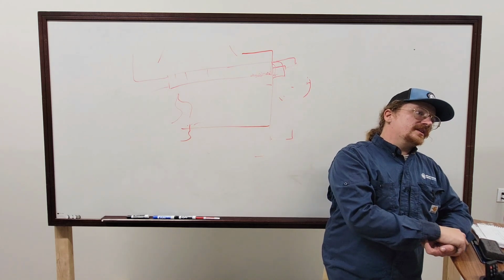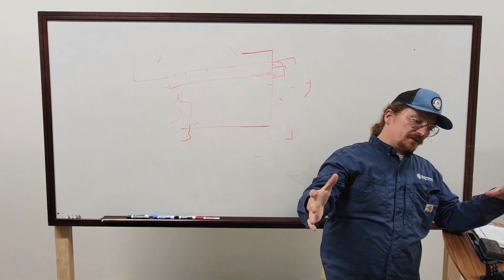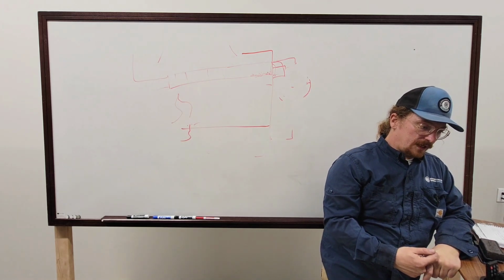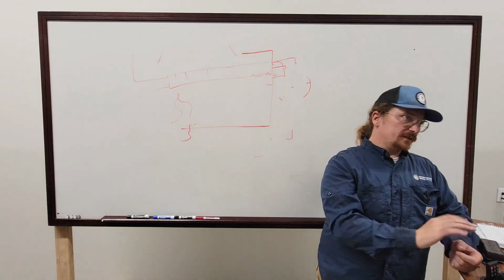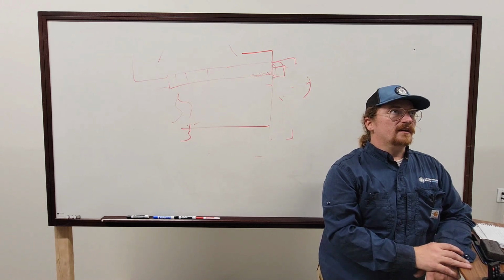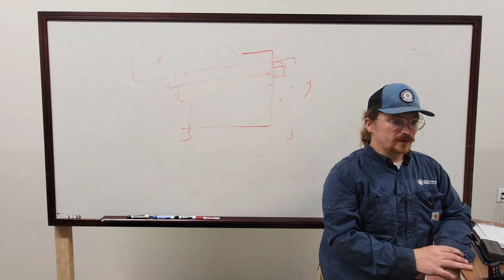A lot of the type that use a burner controller, what's that called? The modular system where the burner system is separate, it can be bought separate. You'll check the linkages on that. I now can understand what the linkages, for the most part, should be doing, but I think it's just checking, making sure that they're there and they're tied. Fan amps, if there are any fans. But I think the overall is checking the safeties, and that's one of the more involved, mind-scratching things that you have to do that's unique to a boiler: verifying the safeties.